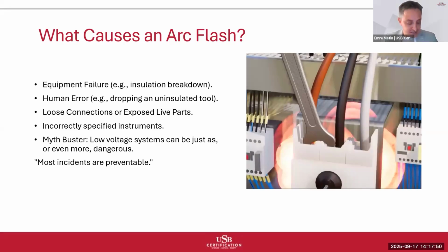Now, here is a critical myth we need to address. Low voltage systems can be just as dangerous as high voltage systems. It's very important. Low voltage systems also carry dangers in the arc flash methodology because of the short-circuit currents divided by resistance at the end of the line. I reviewed incidents where 480 volt systems create more severe arc flash conditions than some medium voltage installations. We will see the arc flash labels. You will see the more dangerous low voltage systems compared to medium voltage installations.